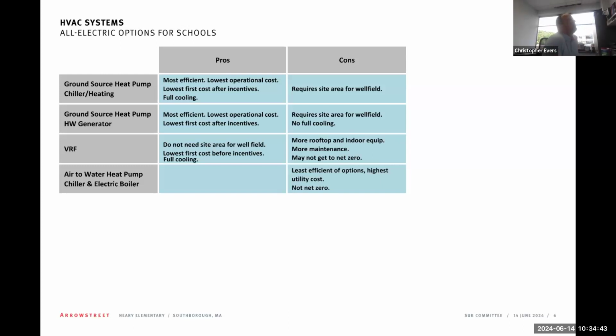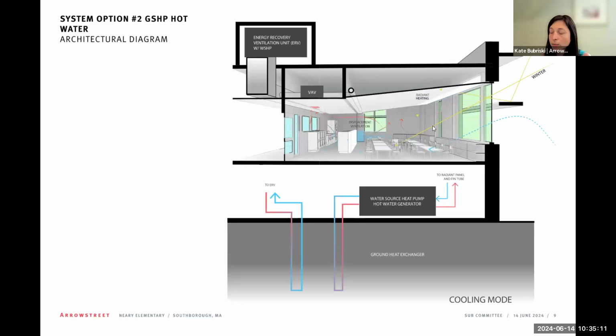One question I have: terminal equipment. So with all these options, the school really will not have a piping infrastructure. Based on those sketches, I'm guessing you're doing terminal equipment. Now you showed supplemental electric heat on the wall space, you showed radiant panels and then a backup heater. Are those radiant panels hydronic or electric? So the radiant panels are hydronic in the ground source system, and they're electric in the VRF system.